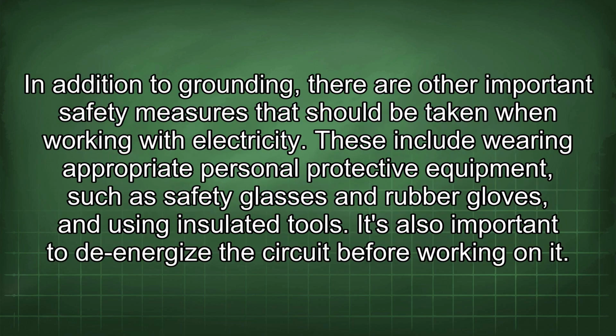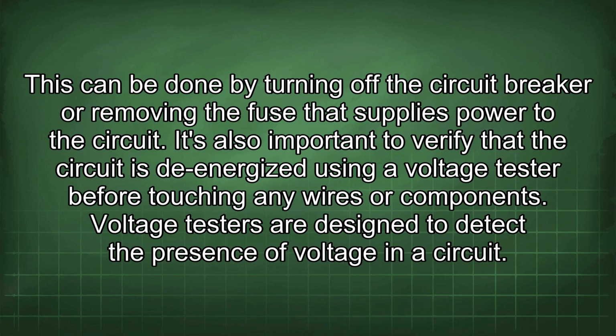In addition to grounding, there are other important safety measures that should be taken when working with electricity. These include wearing appropriate personal protective equipment such as safety glasses and rubber gloves, and using insulated tools. It's also important to de-energize the circuit before working on it. This can be done by turning off the circuit breaker or removing the fuse that supplies power to the circuit. It's also important to verify that the circuit is de-energized using a voltage tester before touching any wires or components.